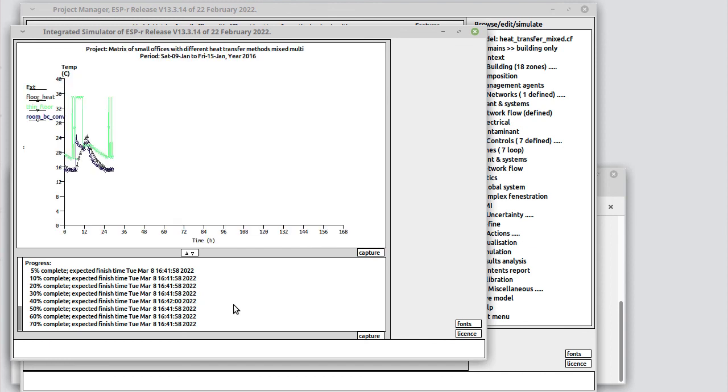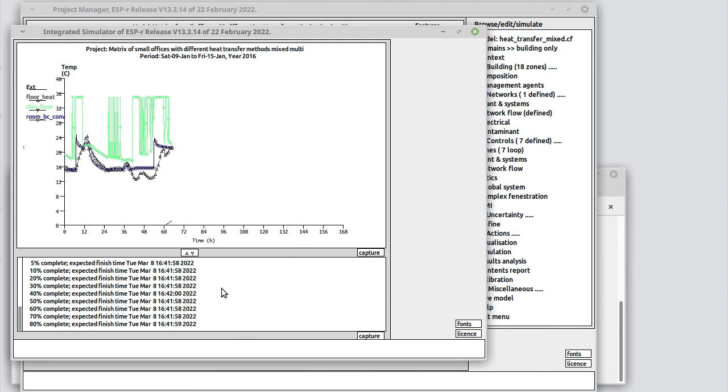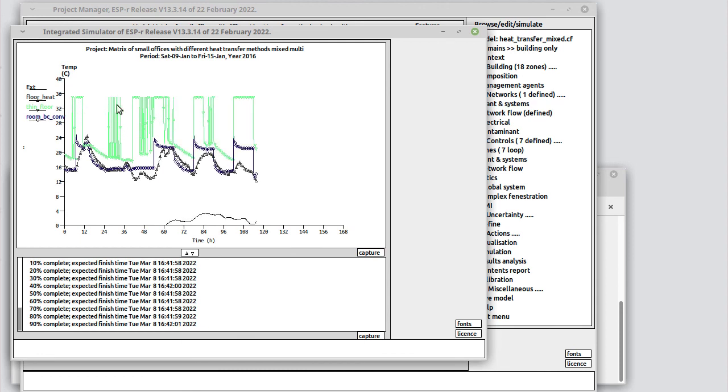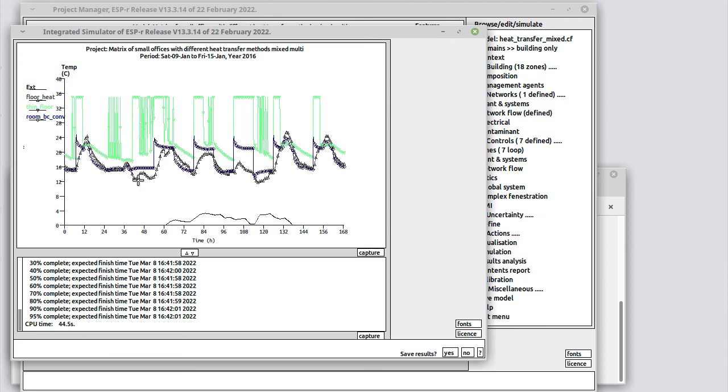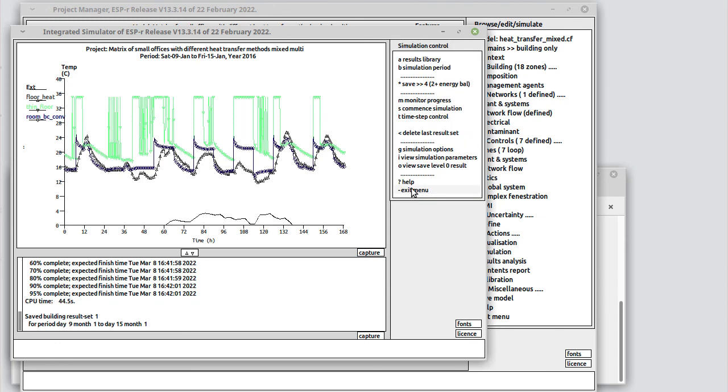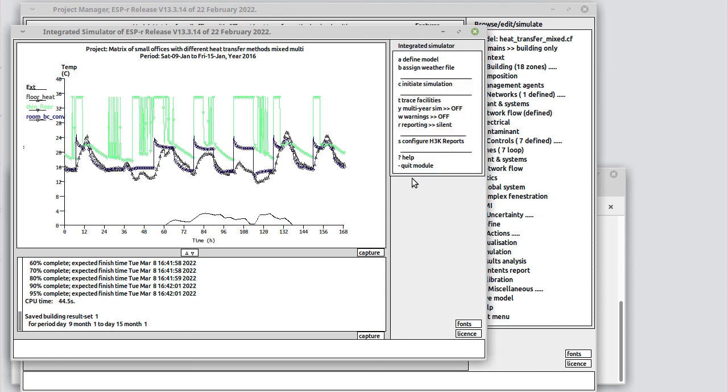Focusing on the floor. Okay, now we've passed the freeze simulation time. We can see the heating coming on in the floor zone and we can see the temperature in the two other zones. Now, one which has a very quick response, well that's the air based system. The one which is lagging, well that's the floor heating system.